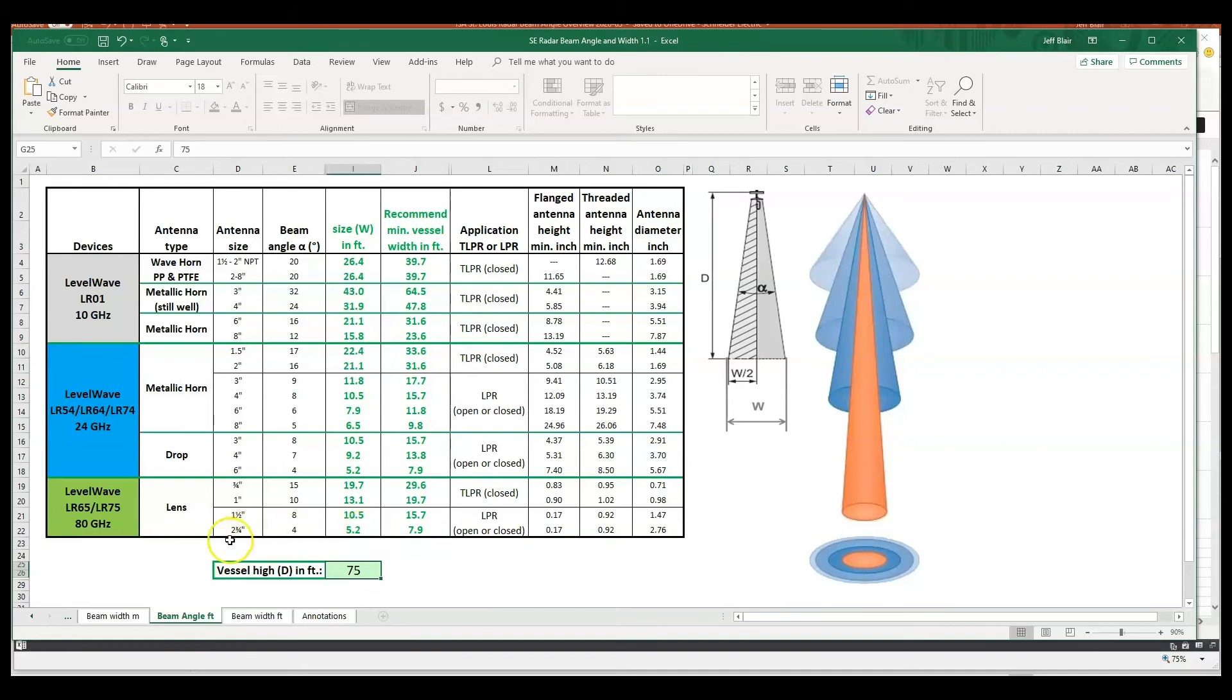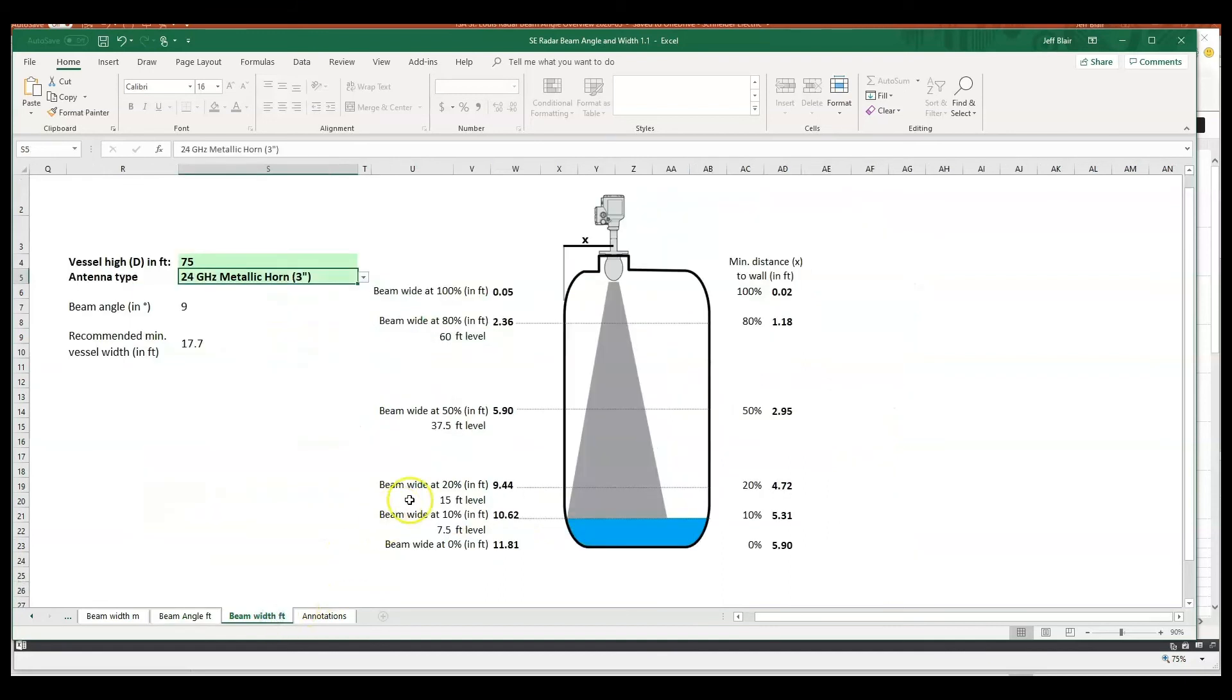So back to - if you remember the nozzle and the valve we looked at - we could actually figure out if we plugged in 75 feet and we wanted to go with the most narrow beam we could find, that would be an 80 gigahertz with the 2 and 3/4 inch lens. We've got our 4-degree beam angle.